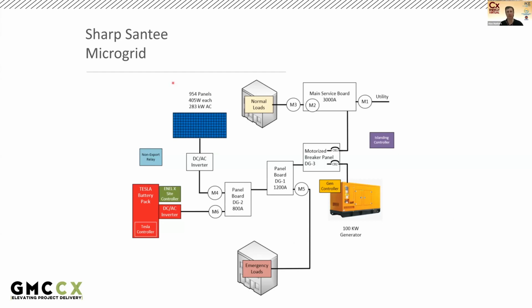There are 4 other main items, which are the non-export relay, the generator controller, the EMS site controller, and the islanding controller. So the non-export relay makes sure that the Tesla battery does not output to the grid. It does this by monitoring meters M6, M3, and M4, and it makes sure that power going out through M6 is less than power being used by M3 minus power being brought in through the solar through M4, which is the available power to normal loads after taking into account the solar power produced. So the main purpose of the non-export relay is to make sure that the Tesla battery does not export power to the grid.